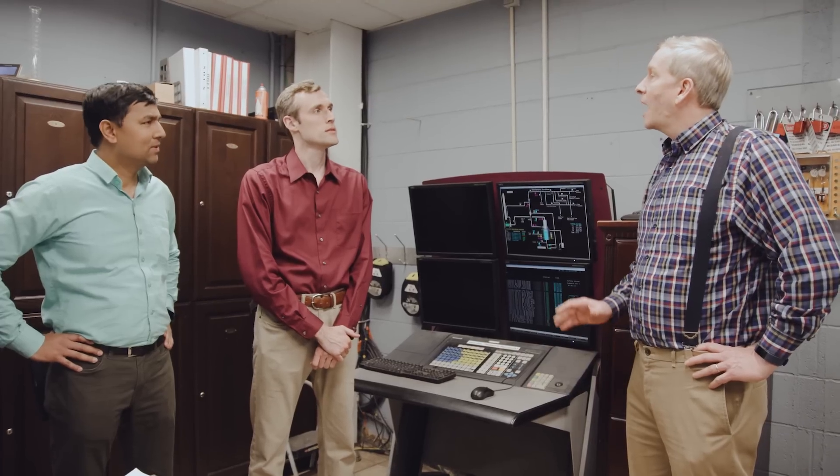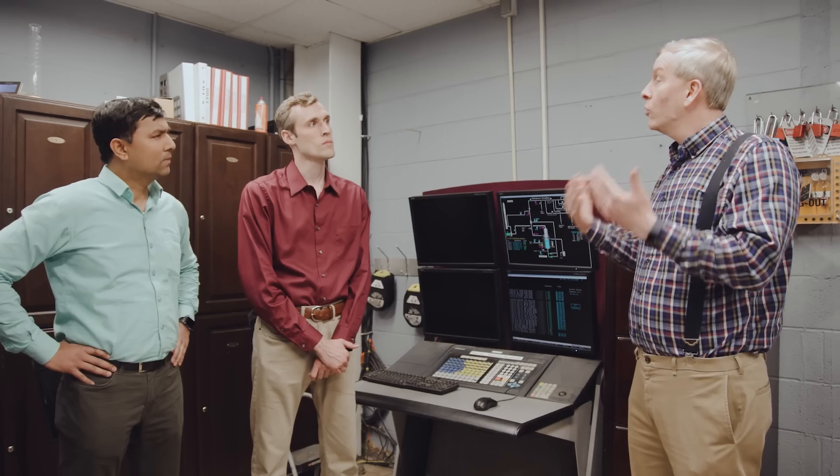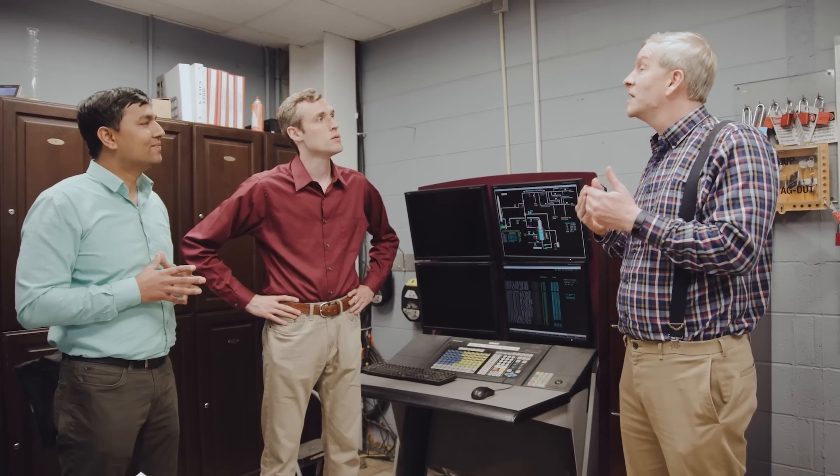This is the team manager's office for the oxidation and purification area of the plant where TiO2 is made. We heard you're collecting a lot of data — temperature, flow, pressure. We have big data that collects all attributes, looks at our production rates and operating conditions, and calculates how much natural gas we should be using on our burners. It tells us if we're using the right amount or too much, and we take corrective actions. Fuel-to-air ratios are automatically controlled to minimize excess energy. We're also looking at whether we can bypass steam entirely for certain parts of the process — if we can, our energy cost and CO2 emissions from that go to zero.